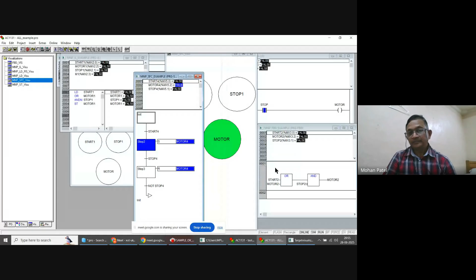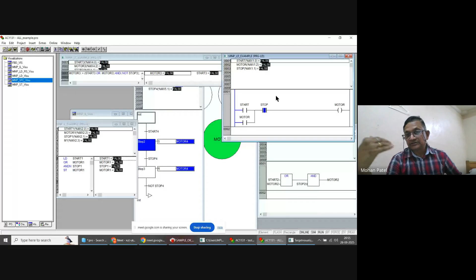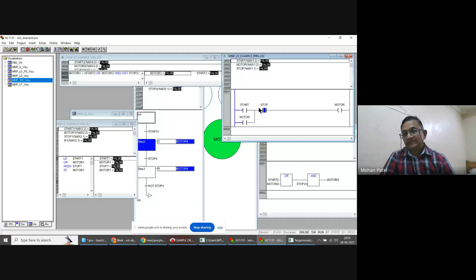All languages have certain plus and minus points. Ladder diagram language is very easy to understand and easy to trace out; if we are stuck in a program, we can easily visualize its status and trace out and solve the problem. However, the limitation is that if we have a ladder of 1000 rungs, the execution time will be more. Function block diagram language, FBD, has a slightly lesser execution time, but it's very difficult to trace out the problem if something is not working.